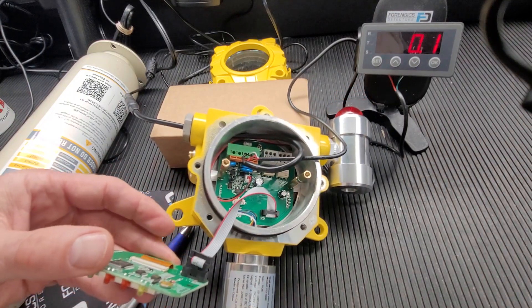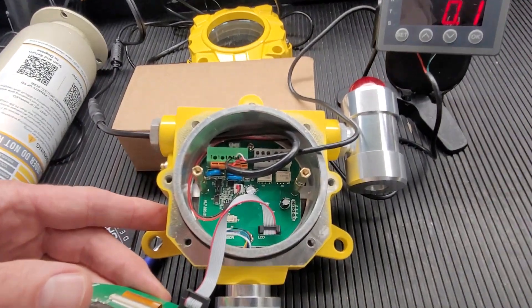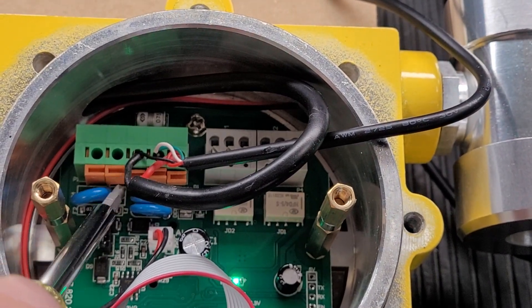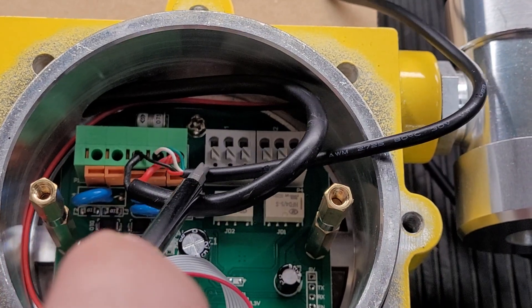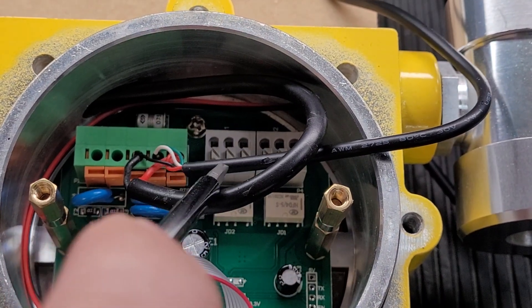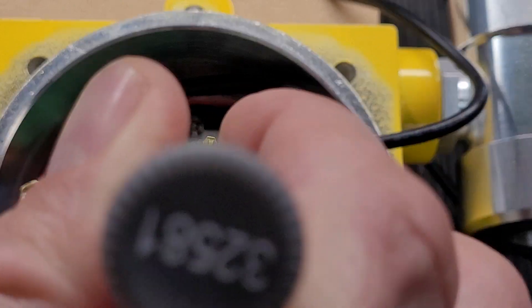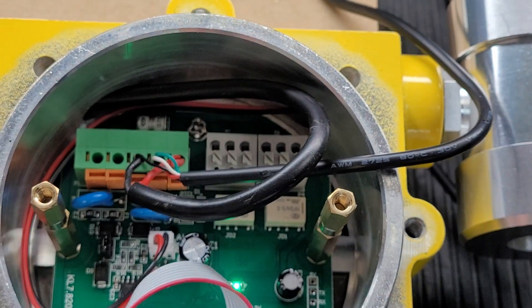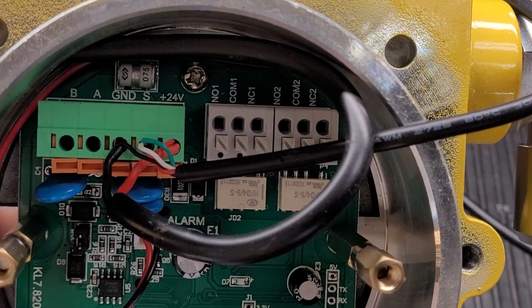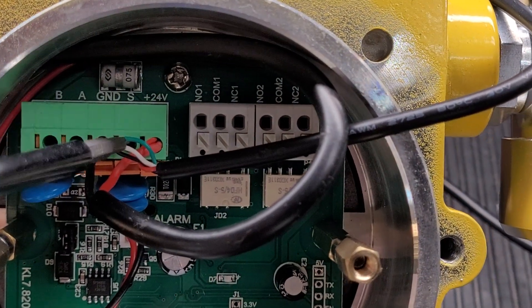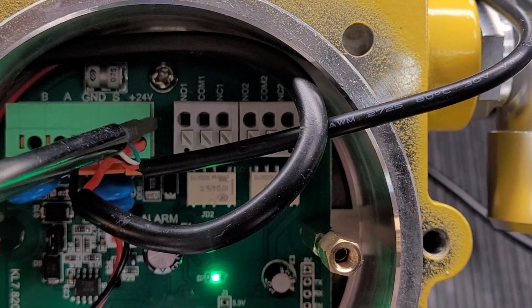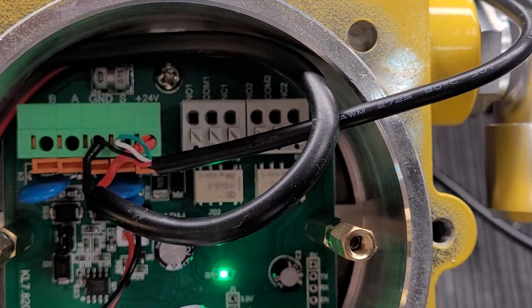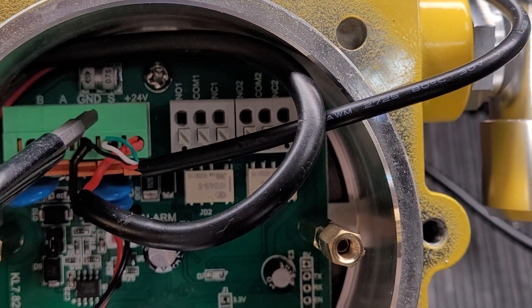Now, if you look carefully, I'm going to zoom in here so you can see what's going on. In our unit, on the black wire, we have our ground. On the farmost, we have our plus 24 volt DC. And in the middle, right there, we have, as you could probably see, it says S. That's the middle, right there. That's the second terminal from the right. One, two, three. Two, the second from the right is our 4 to 20 milliamp signal. And ground.